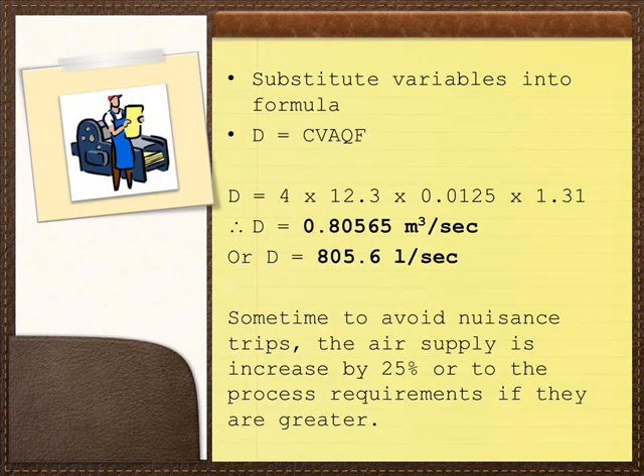The variables are substituted into the formula. D equals 4 times 12.3 times 0.0125 times 1.31, which equals 0.80565 cubic metres per second, or 805.6 litres per second. Sometimes, to avoid nuisance trips, the air supply is increased by 25% or to the process requirements if they are greater.